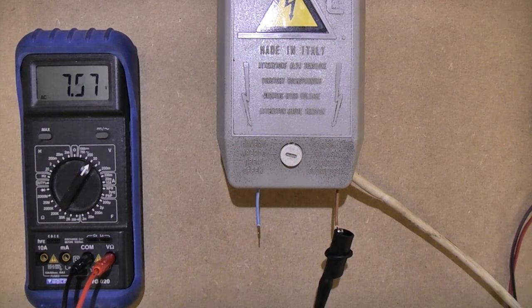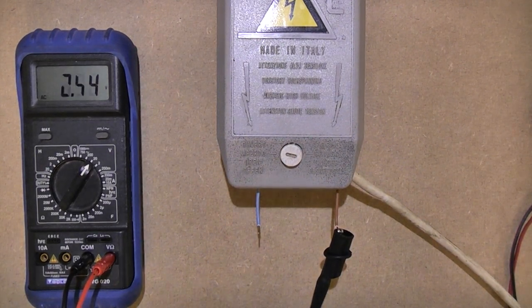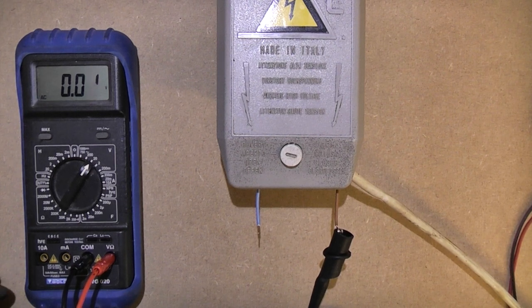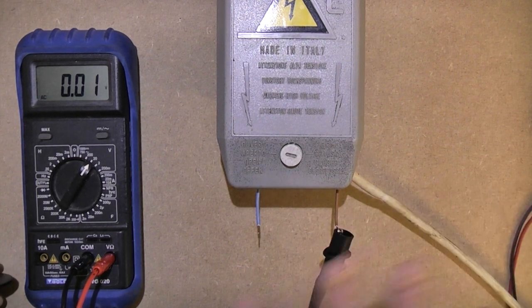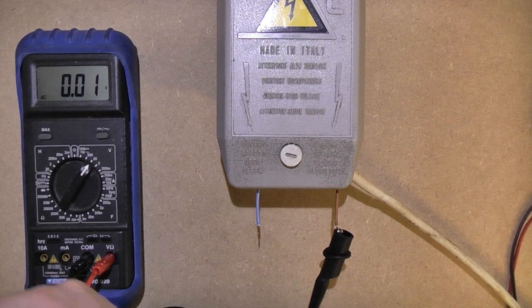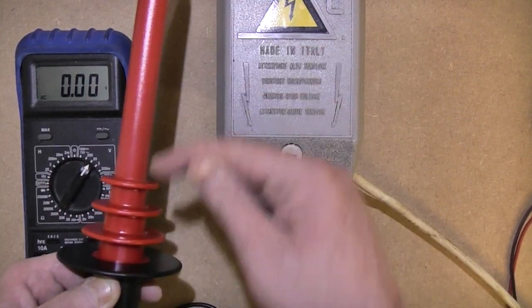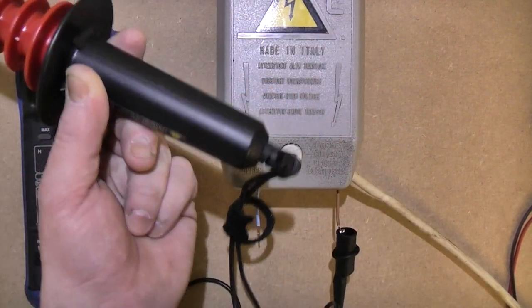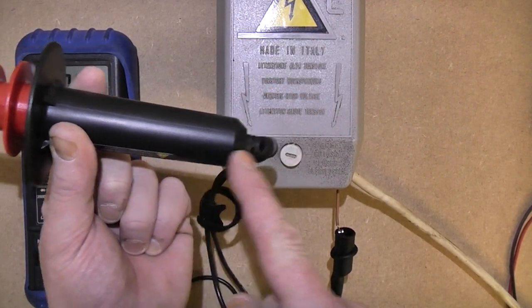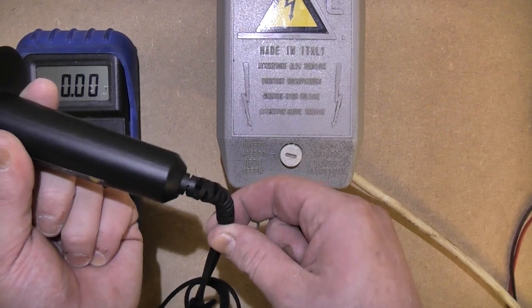9.27 kV. Right, under no circumstances should you repeat something like that because you've got that distance there to the top. You've got that distance from your hand to there and this isn't rated for 5 kV.